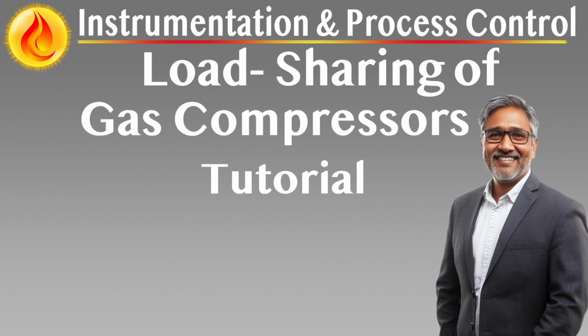Control prioritization and flow relief strategy. First line of defense in sustained surge conditions: the cold recycle valve opens before hot recycle valves. This centralizes surge relief and spreads it evenly across the compressor network. Surge protection hierarchy. Hot recycle controllers retain full authority to act if surge continues or escalates. Cold recycle action complements, not replaces, local surge protection. Thermal management. Recycled gas is cooled before being reintroduced, preventing temperature accumulation at compressor inlets. This improves volumetric efficiency and reduces thermal stress on equipment.